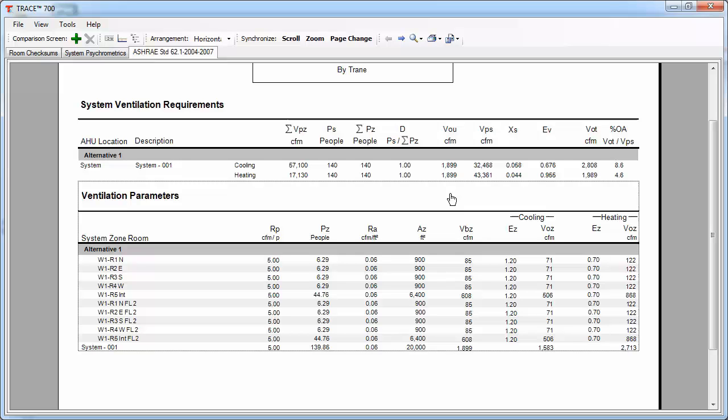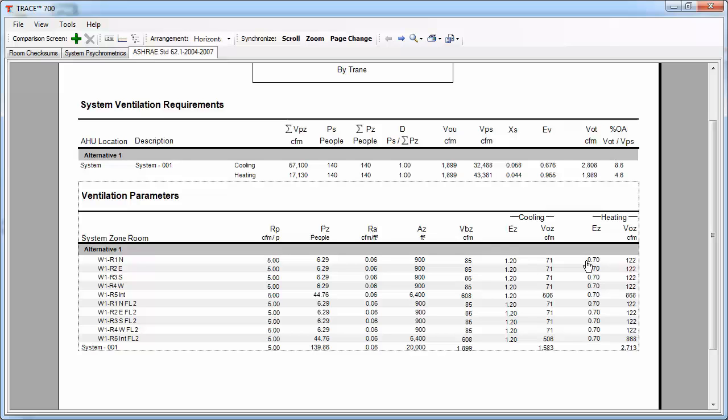Today, I'm going to focus on three, which I find very important for UFAD system design. We'll start off with the ASHRAE Standard 62.1 report, which I use to verify my inputs to the outputs. So, in this case, I wanted to make sure that for my particular spaces, that they match the ventilation rates and the effectiveness values that I've inputted. So, for cooling Ez and heating Ez, they match at 1.2 and 0.7. And then for my RP and RA values, I have 5 and 0.06. So, I can confirm that TRACE has the correct values, and it's going to be using the ASHRAE Standard 62.1 calculation based on these ventilation rates.